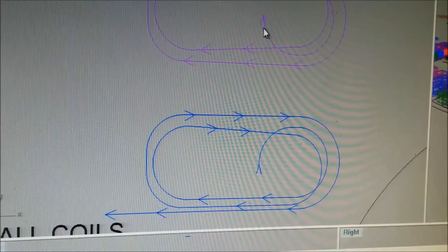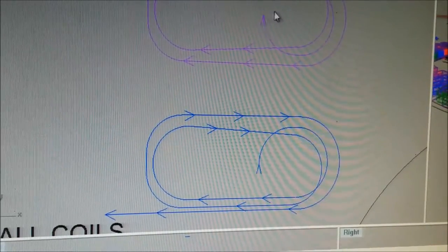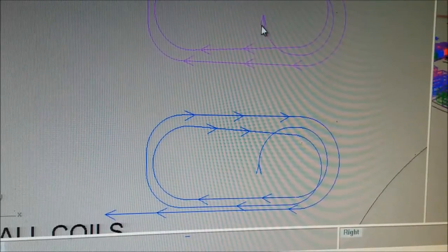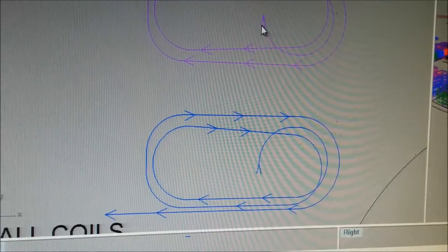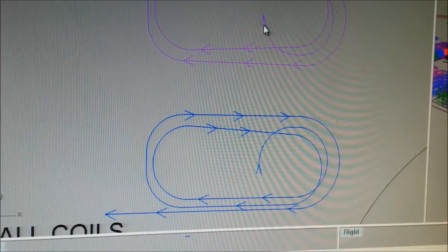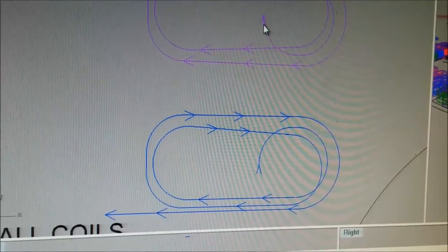And if you have the start of your wires, like we're going to have six wires here, they have to be connected together at both ends, because you need the six conductors to carry the amps. One conductor's not enough amps. It's only, what's it? I forget now. 3.9 maybe, or two point something.